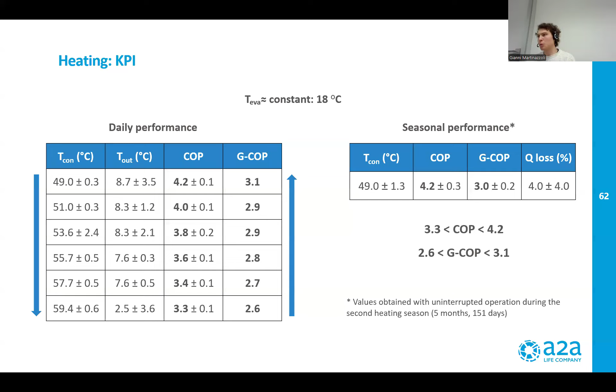We perform also tests under off-design conditions, where we change the temperature of the evaporator to simulate different kinds of low temperature heat, with temperatures between 10 and 30 degrees, and with different temperature at the condenser to simulate the different kinds of heating system, from radiant panels to fan coils and radiators. So temperatures at the condenser were in the range between 40 and 65 degrees.